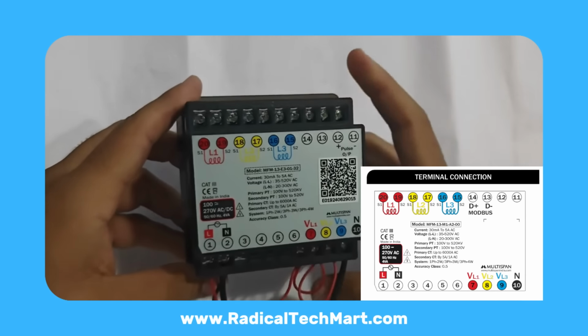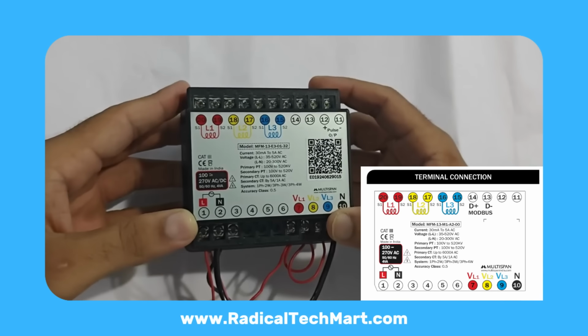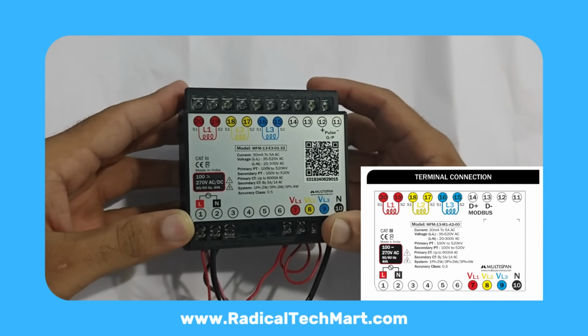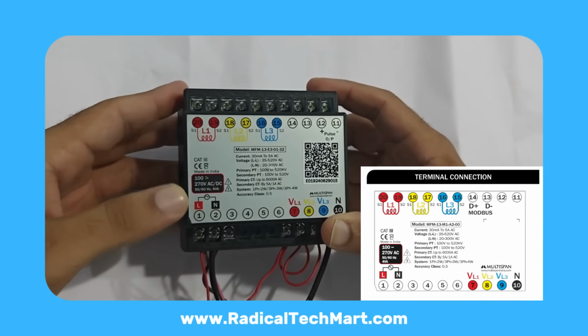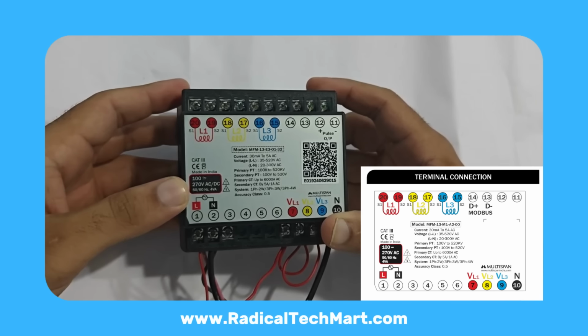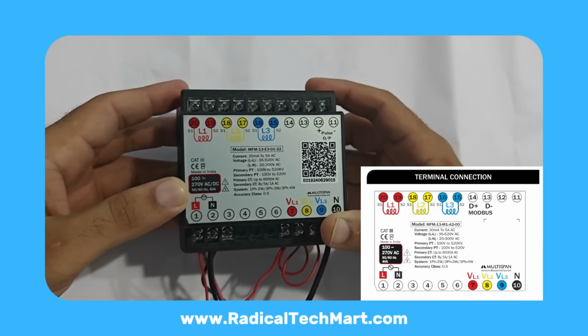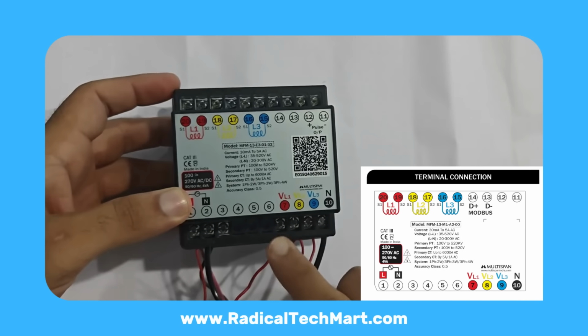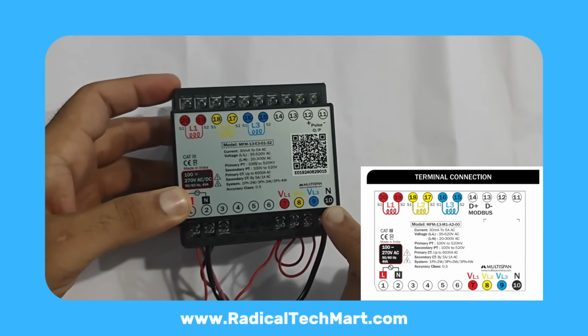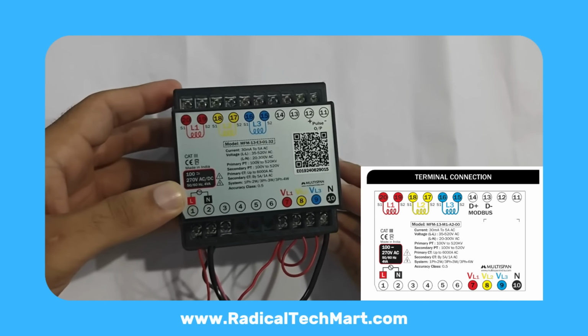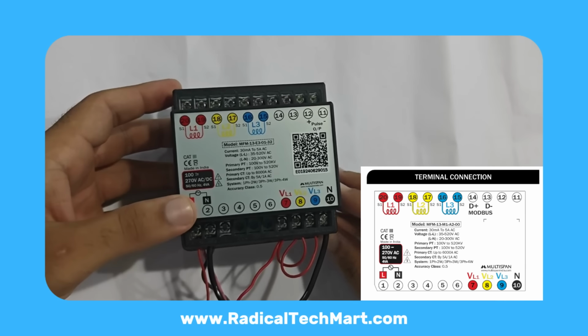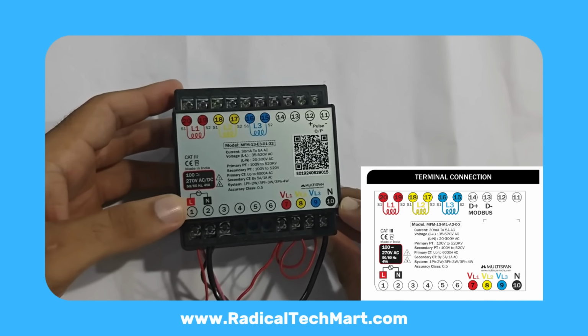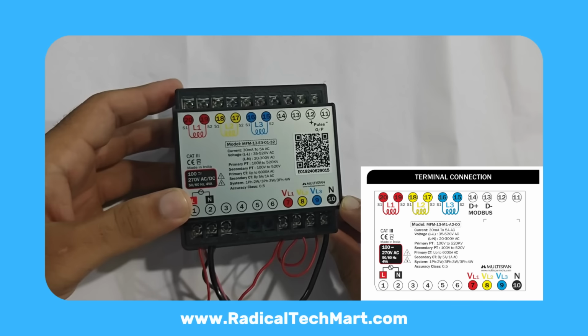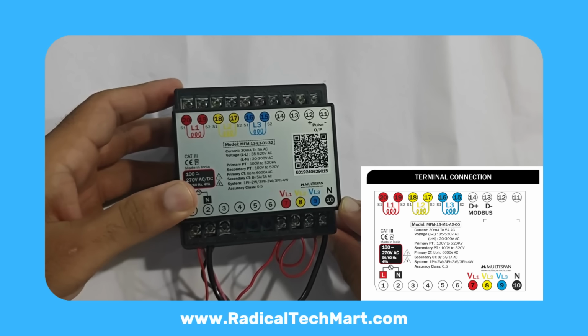On the back side, terminals 1 and 2 are for the auxiliary supply, line and neutral. You can give a variable supply from 100 to 270 volts AC or DC. Terminals 7, 8, and 9 are for the three-phase voltage inputs: 7 R phase, 8 Y phase, 9 B phase. Terminal 10 is the system neutral connection.